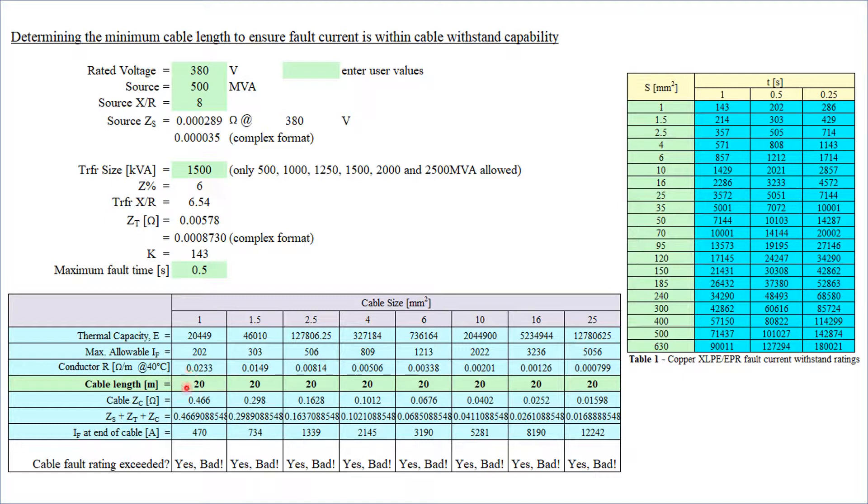Now let's suppose my cable length is only 20 meters, so I have a pretty short run of cable. My cable impedance is 0.466, and I can then calculate the total impedance from the source to the fault point, which is given by this value. So the fault current is 470 amps—that's the through-fault current for fault at the end of my cable. We can see 470 exceeds 202, so cable fault rating exceeded. Not good.